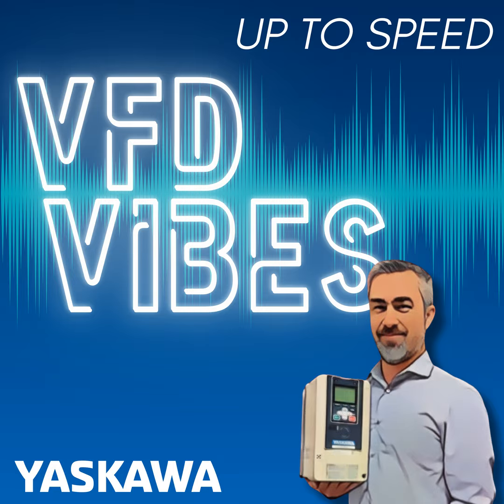So even in an ungrounded system, I've heard of people walking out and hanging a voltmeter on there and measuring line-to-ground voltages of 277 volts, even when the system is ungrounded, because the parasitic capacitance of the conductors, of the conduits containing them, the wireways and so forth, tends to balance the system. So sometimes that works for you and helps things out in an ungrounded system. Yeah, I don't know if I can wrap my head around how exactly that works, but it's funny how these things tend to have a way to work themselves out.